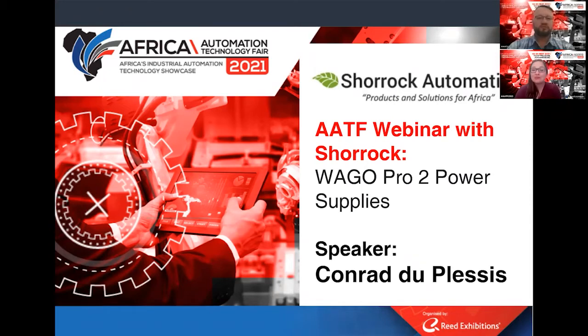This webinar will focus on WAGO's Pro 2 power supply range and how WAGO has set a new benchmark in industries with communication and parameterization possibilities. With quantitative and qualitative requirements becoming stricter by the day, control cabinets are undergoing increasing transformations. Greater networking, rising energy costs, and increasing customization require economic flexibility, speed, and a minimal footprint for control cabinets. WAGO's Pro 2 power supply range is a true power efficiency champion with up to 96.1% efficiency, making this the new heart of your control cabinets.